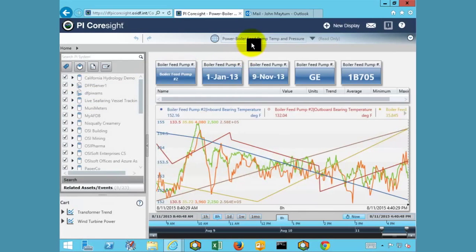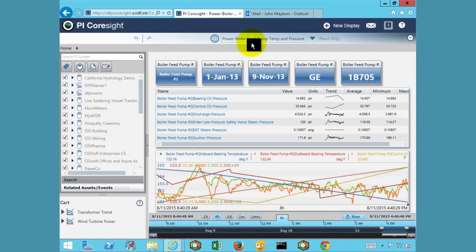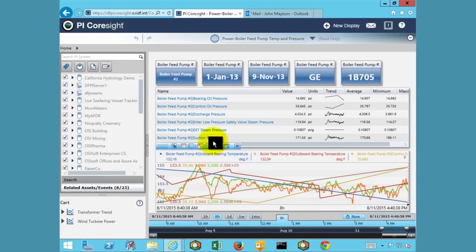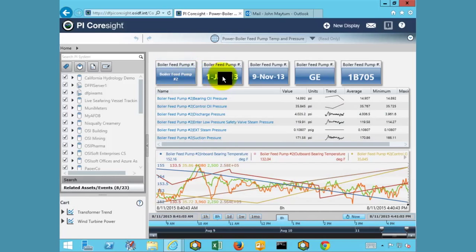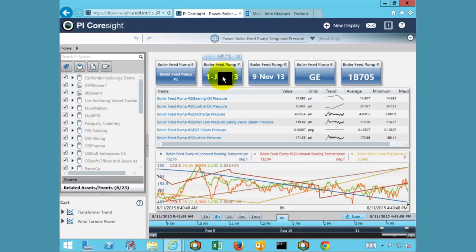In our case, we have opened up a display pertaining to a boiler feed pump. From this display, we can see current and historical conditions for the equipment. Time series information, such as bearing temperatures and pressures, can be seen along with nameplate information and other useful data that can be used to diagnose issues for root cause analysis or to monitor the equipment in real time.